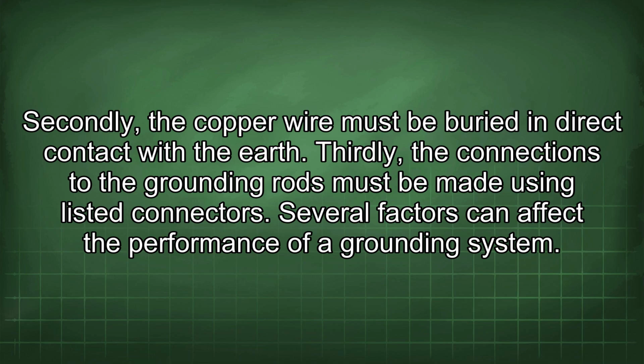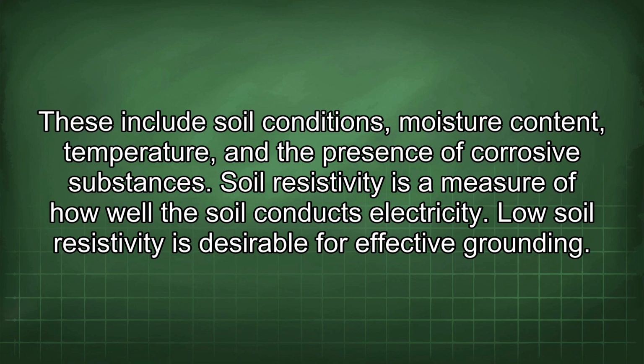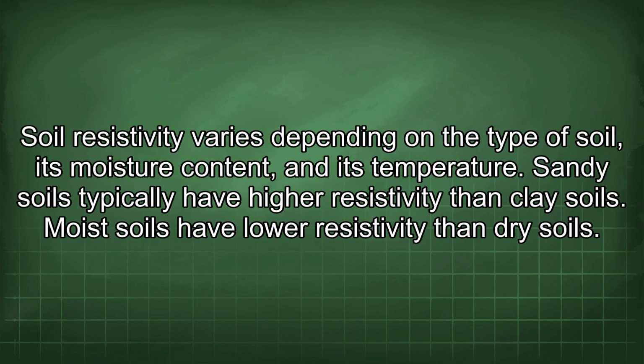Several factors can affect the performance of a grounding system. These include soil conditions, moisture content, temperature, and the presence of corrosive substances. Soil resistivity is a measure of how well the soil conducts electricity. Low soil resistivity is desirable for effective grounding. Soil resistivity varies depending on the type of soil, its moisture content, and its temperature.